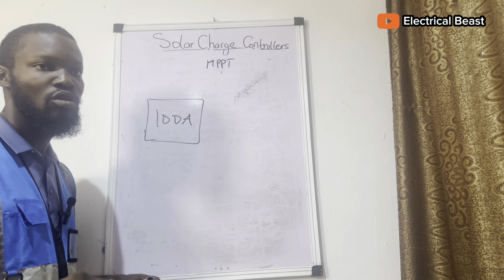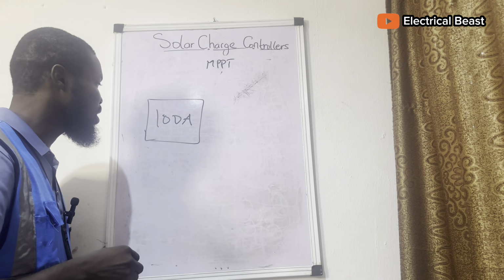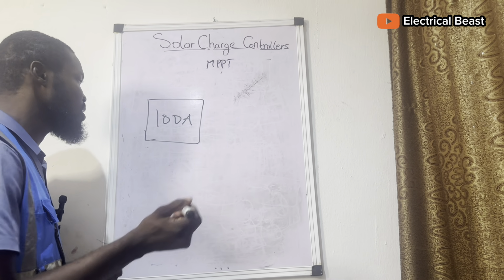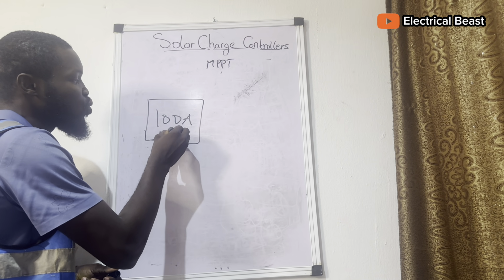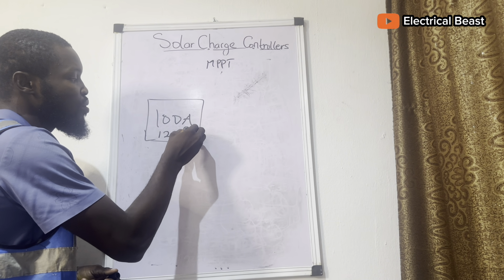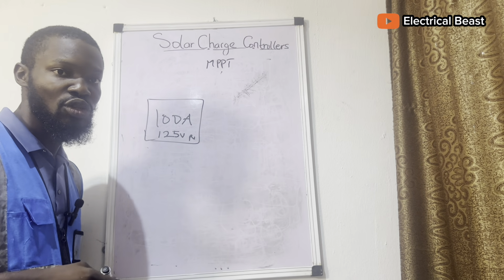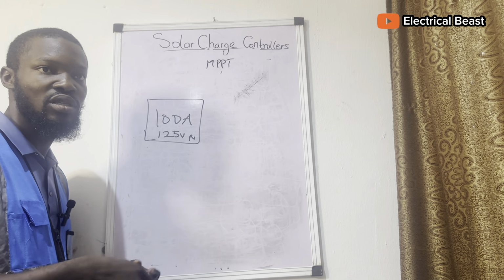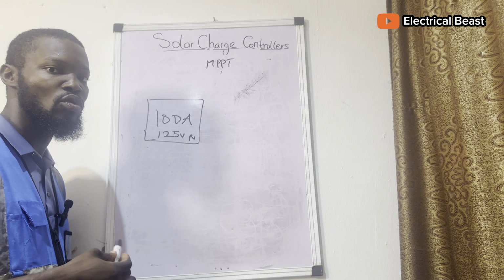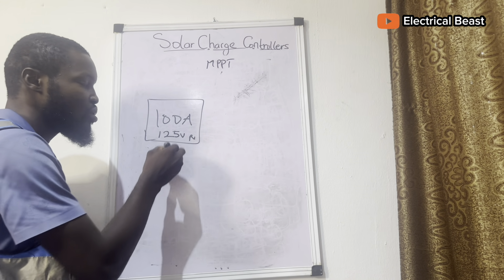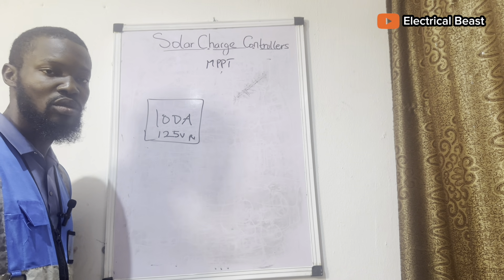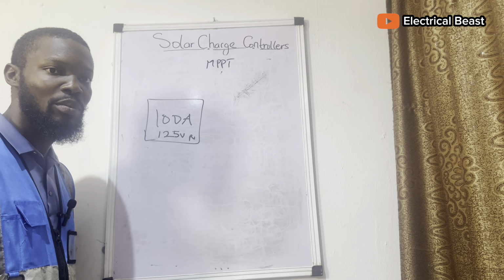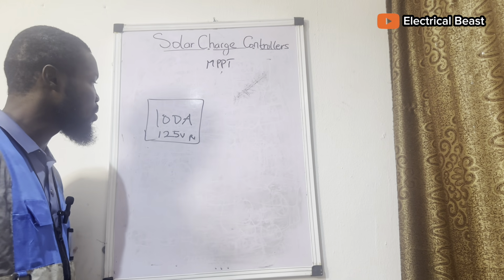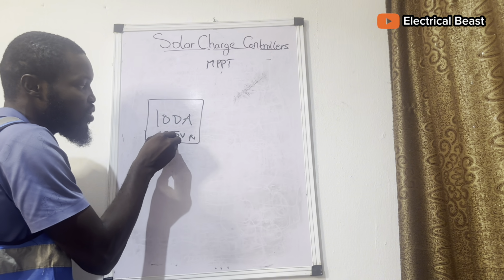Now, for an average MPPT controller of 100 amps, you can have a voltage range of, let's say, 125 volts PV. All these specifications are written on the nameplate of the controller for you to see, to observe and know what you are doing. Now, if you have 125 volts, it means you can connect higher wattage solar panels or higher voltage solar panels within this range. You are going to work within this 125 volt PV and 100 amps range.